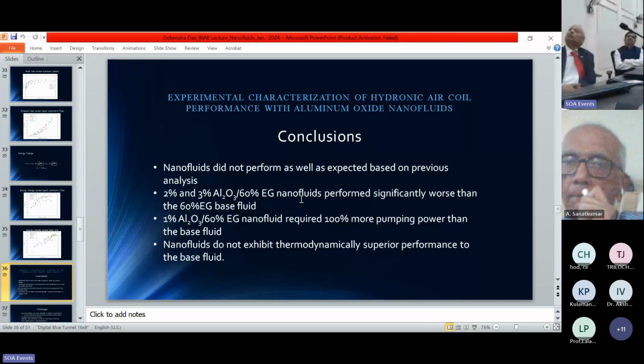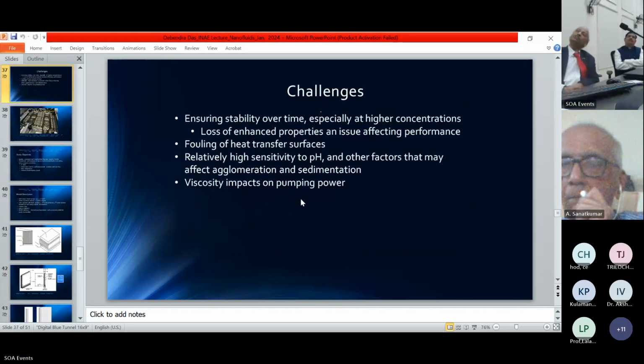2% aluminum oxide performs significantly worse than the pure liquid, which is best. 1% aluminum oxide required 100% more pumping power due to increased viscosity from particle agglomeration. Nanofluids do not exhibit thermodynamically superior performance based on exergy analysis - the available energy associated with heat transfer from pure liquid is better than nanoliquid. These were some of the disappointments. So upon analyzing our data, we identified these challenges.